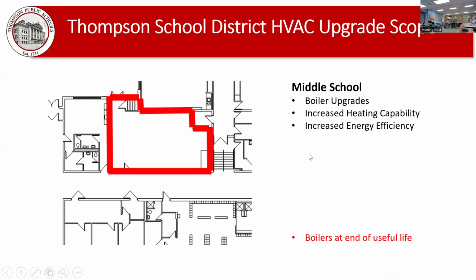Over at the middle school, boiler upgrades. Right now you have existing boilers at end of useful life, beyond useful life. New boilers within the boiler room will pick up all the heating, with all the piping existing to remain. It's going to be an in-kind replacement of boilers. We did upsize those a tick because we've added some additional units at the very end that will come off of those boilers, and then basically keep the work in here with the exception of that piping. Basically minimize the scope.